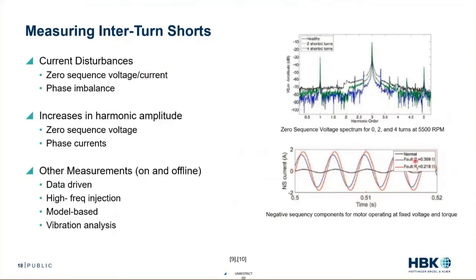And I have a couple different faults. And we can see a really big negative sequence voltage and current. So this is pretty dramatic — this is a really good indicator. And we can watch this creep over time. If we start to have a little short, we can see this. Over time is relative, but about 50 seconds before a major fault, you can see that start to creep. That's really good information.